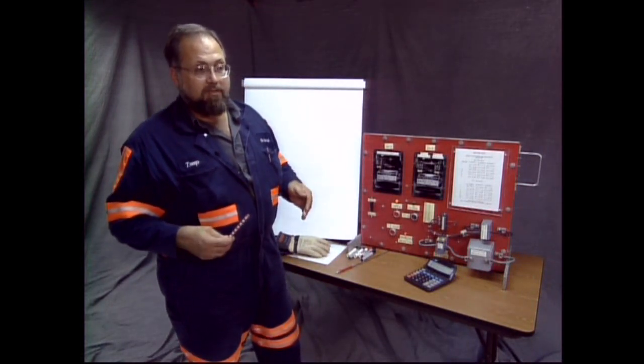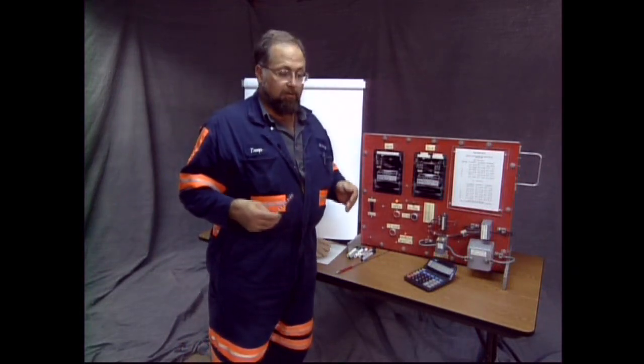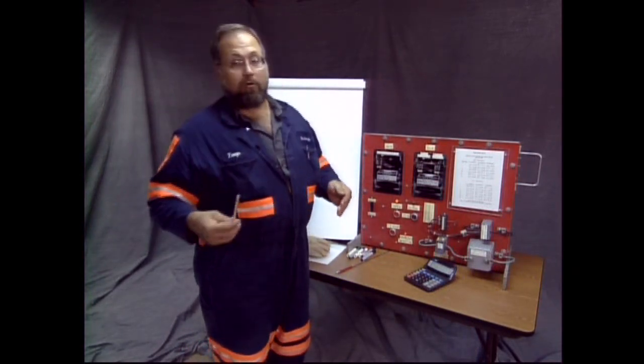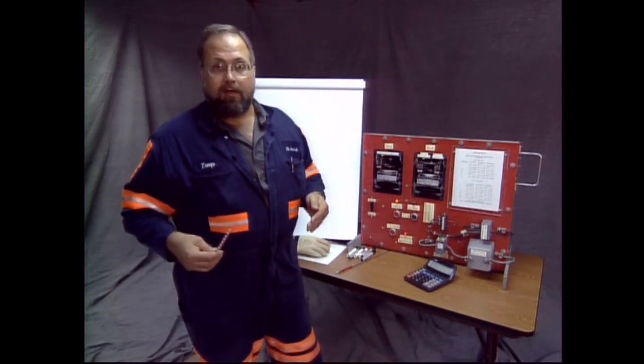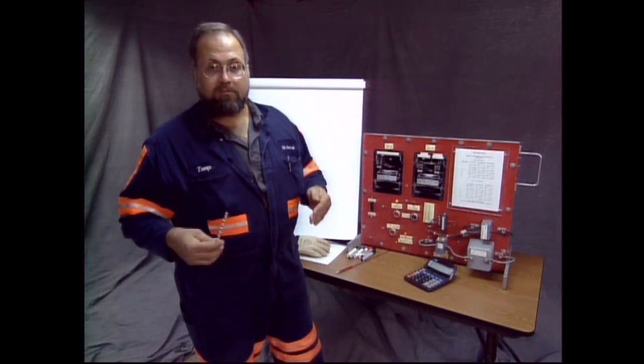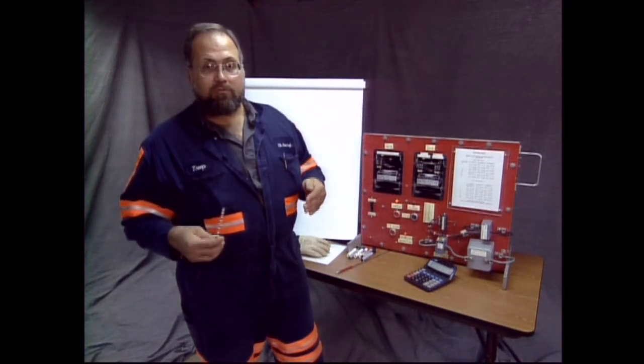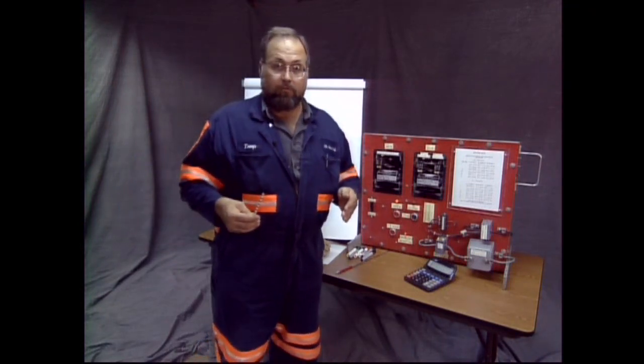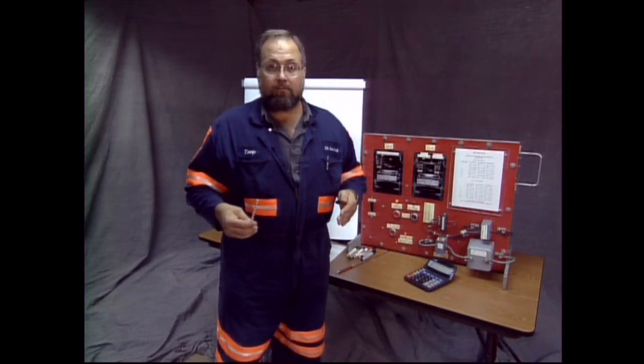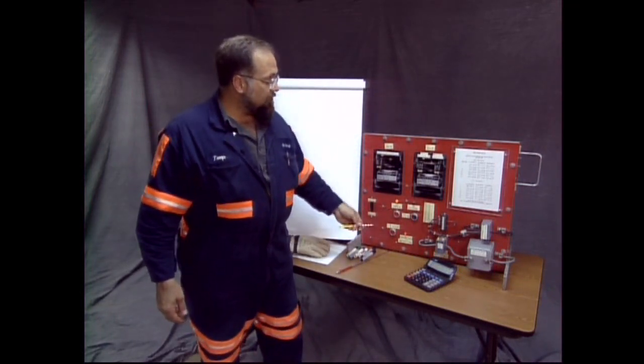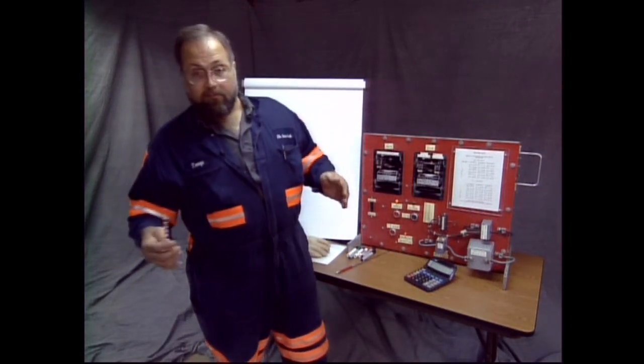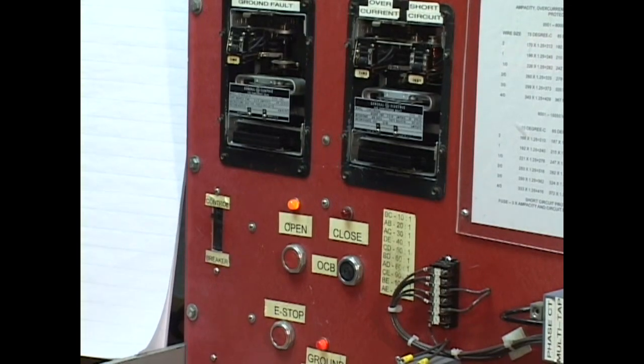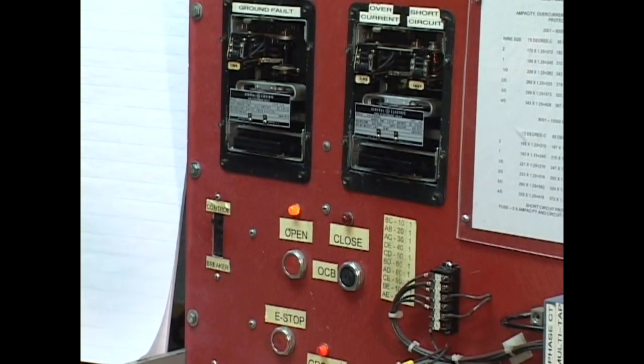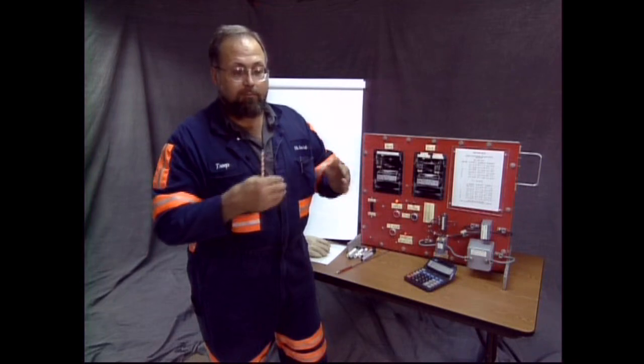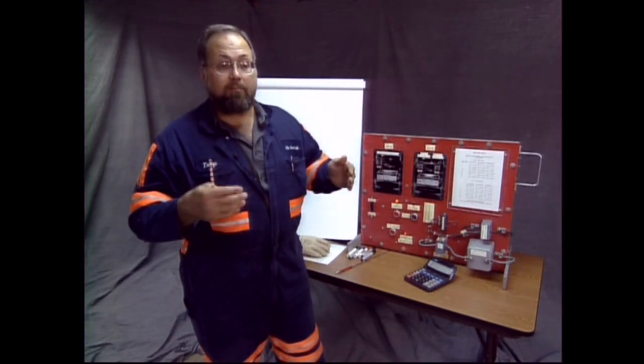But let's talk about our safety here for just a bit. Before you're going to do any high voltage work, any high voltage cable work, a termination, a splice, to bring a transformer online, any of these things, you must, this is a must, follow safety rules to the strictest possible level. You want to definitely open a visual disconnect. Now, as you can see, I opened this breaker by pressing that button and a breaker dropped. That's not a visual disconnect. The light is visual. You're pushing a button. You see which button you're pushing, but it's not a visual disconnect. The light indicates that it's off, but you don't see a separation between the conductors, okay? You don't have a visual separation that you can look at and see, I'm disconnected from this source.